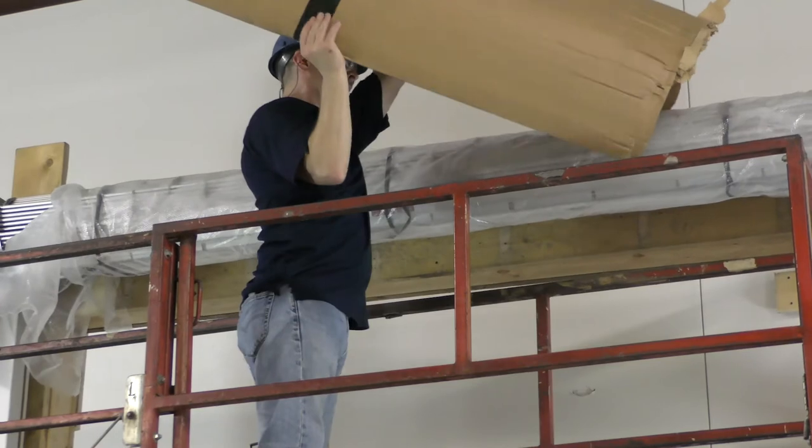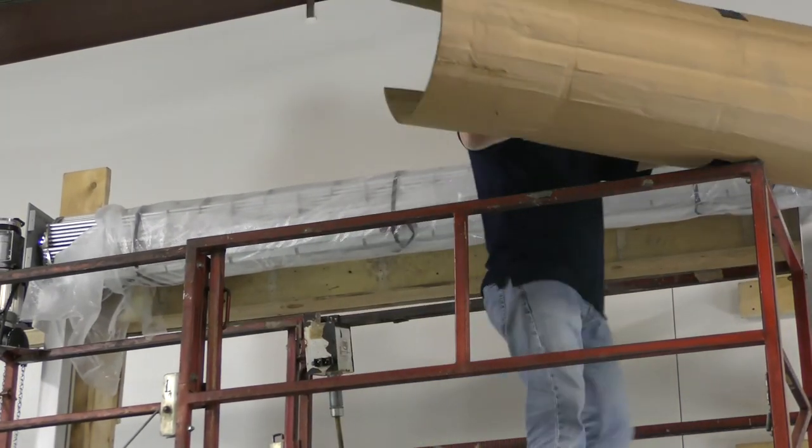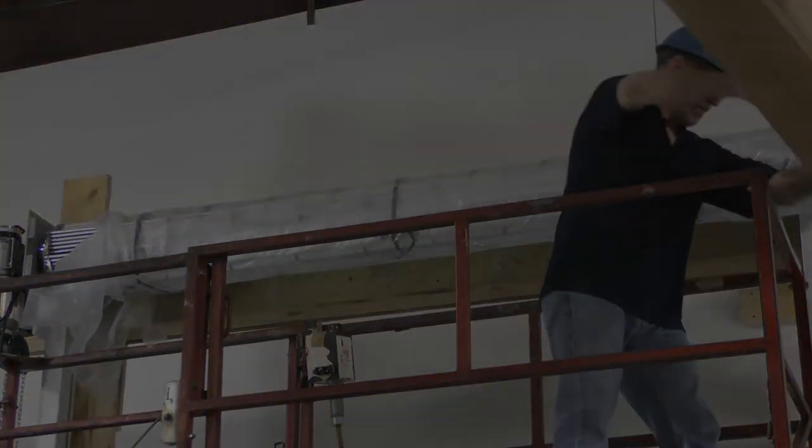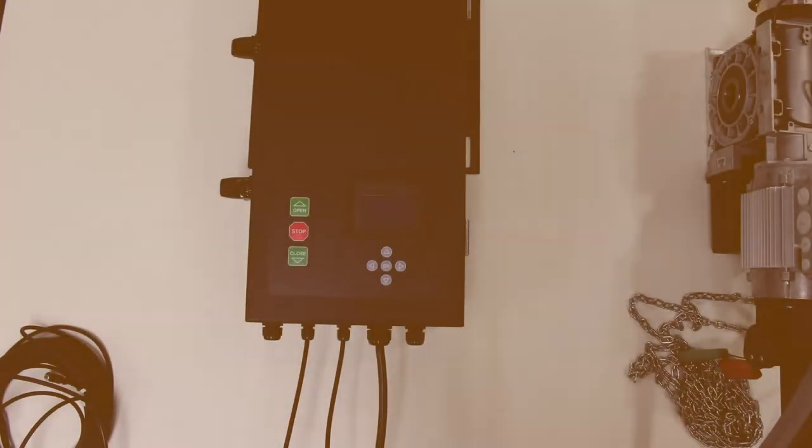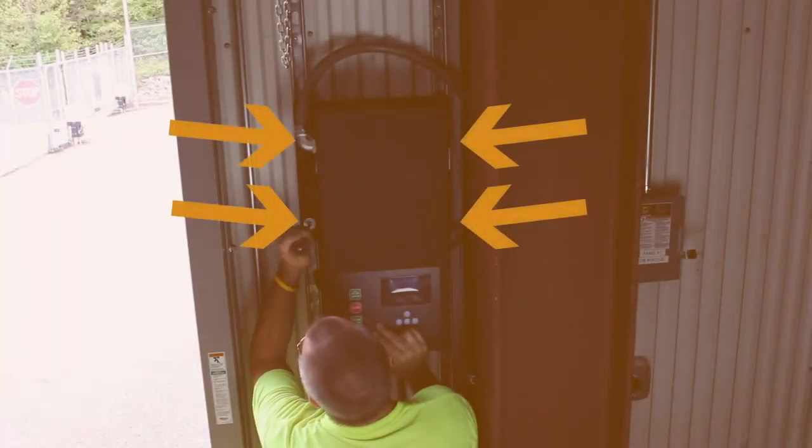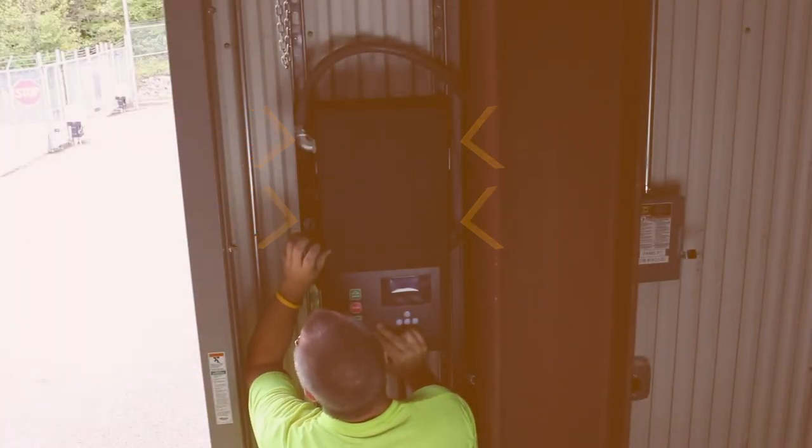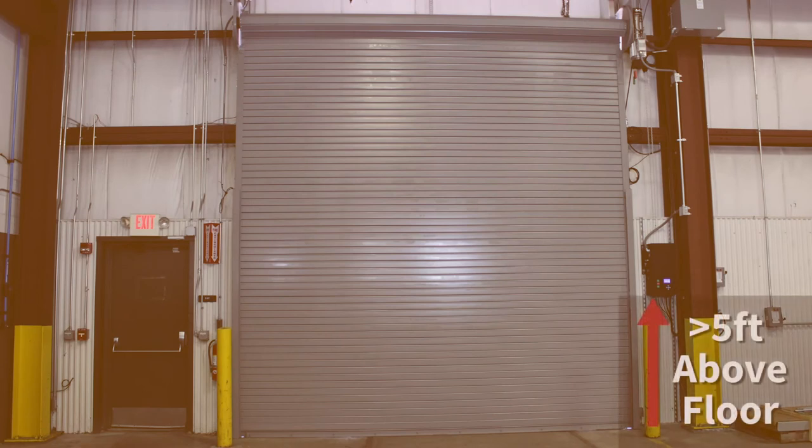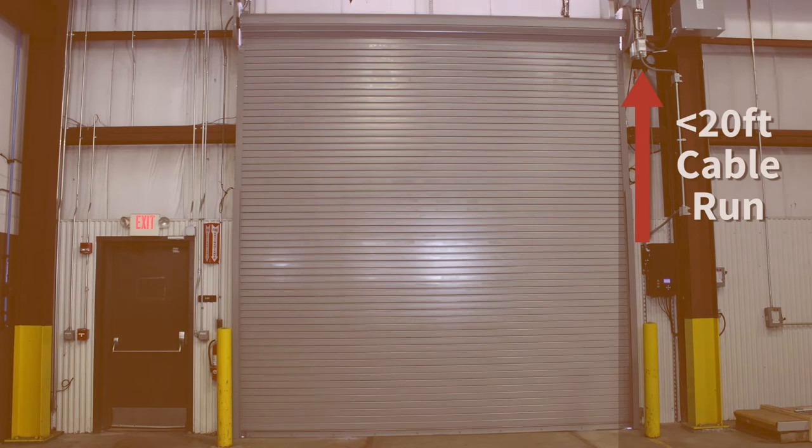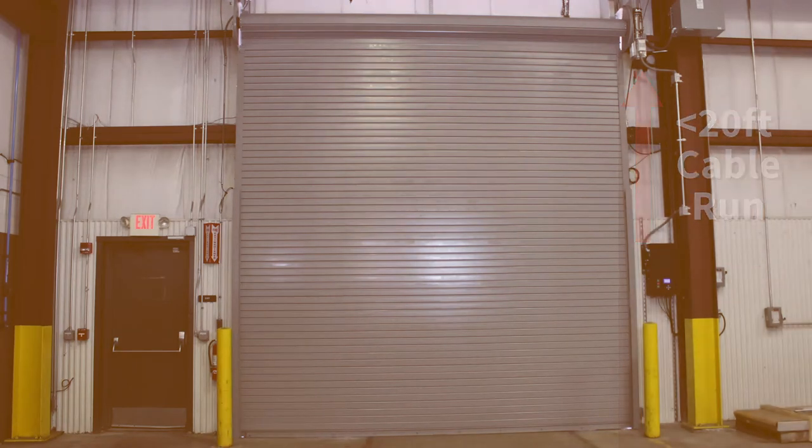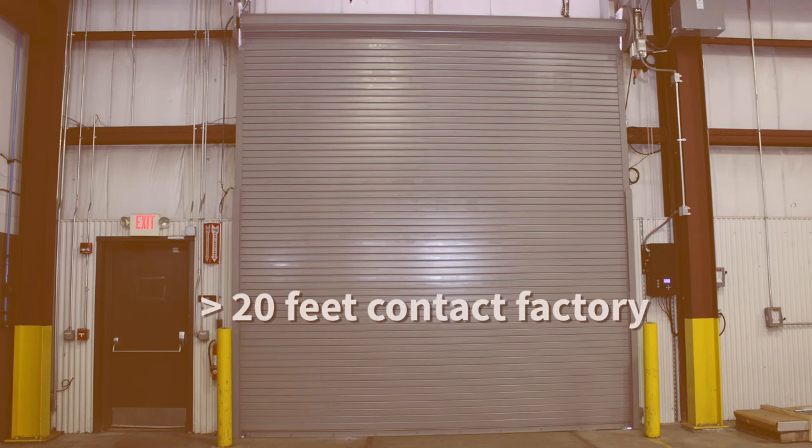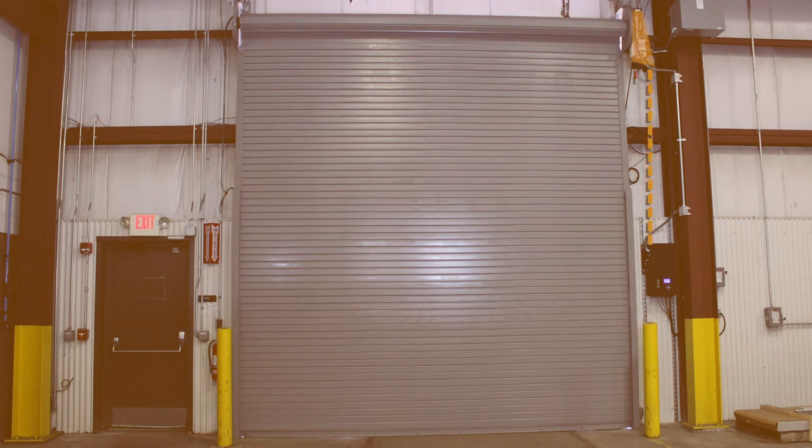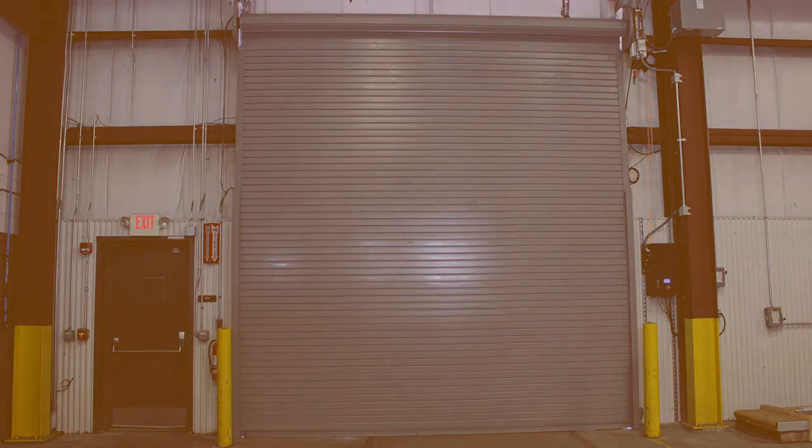At this time, you need to install the Apex Smart Controller control panel. Here's how it was installed for the 300 series door. When you look at the Apex Smart Controller, note that there are three wires already attached. Do not remove them. The control panel is mounted to the wall using bolts. Mount the panel with control buttons at least 5 feet above the floor. Make sure the wire run from the operator and control panel is no longer than 20 feet to maintain warranty. Distances of longer than 20 feet may be possible, but would require special cabling and must be factory supplied or specified to maintain the manufacturer's warranty.